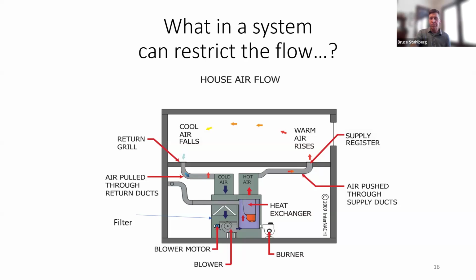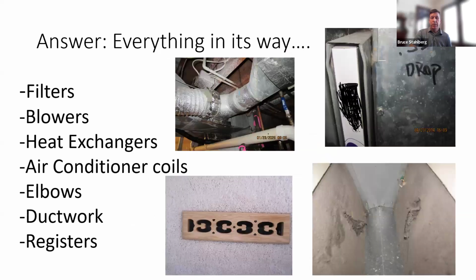There are all kinds of different things. We have registers, ductwork, filters, coils, many different things. All of these things create pressure differences in the system, and we have some selection choices we can make on some of those. Everything that gets in the way of the airflow will create some resistance.